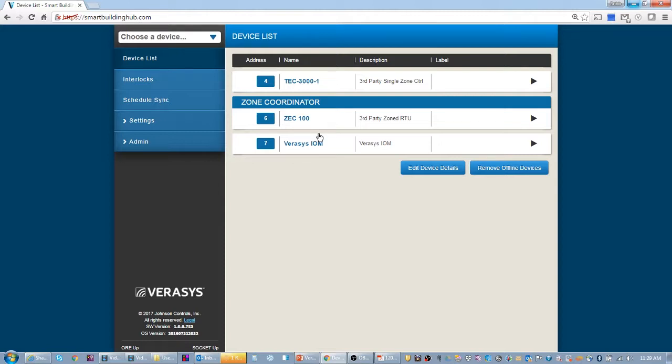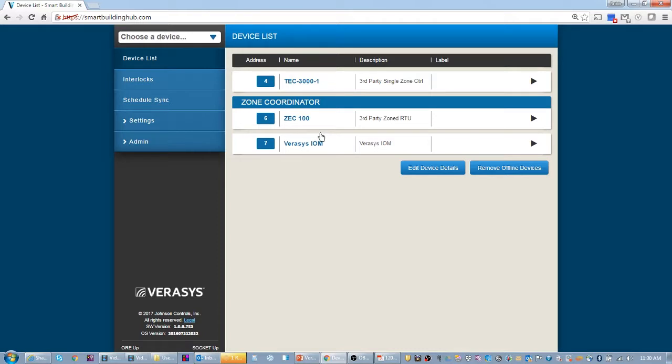This is the way I like to set up zone coordinators and changeover bypass systems and multi-zones. First start by getting smart building hub hooked up to the zone coordinator and then the next device that you want to bring on is the unit itself, whether it be a ZEC 100 or a smart equipment rooftop unit.